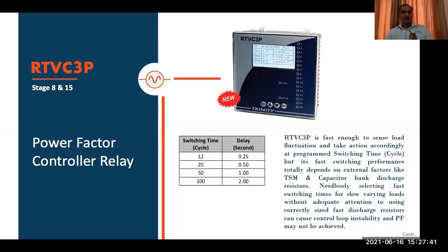So we developed this relay RTVC3P, which can give you switching from 250 milliseconds. So 250 milliseconds, 500 milliseconds, 1 second, and 2 seconds. So up to 2 seconds you can have 4 switching times, and the minimum is 250 milliseconds. So for all real-time power factor correction panels, RTPFC panels, wherein you are putting in thyristors, wherein we are putting capacitor banks with discharge resistors, and for operation of those thyristor modules in real time. And one good advantage with this relay is that we don't need any buffer card to convert the thyristor output as per relay. So it can directly accept your thyristor output, and you can directly plug into the relay. So there is no additional buffer card required.